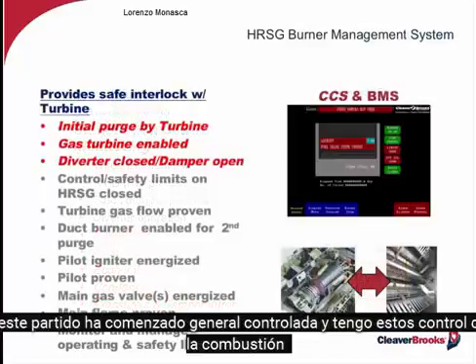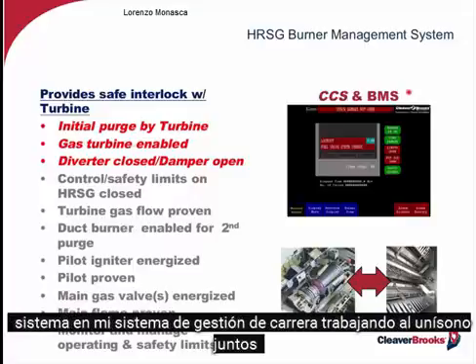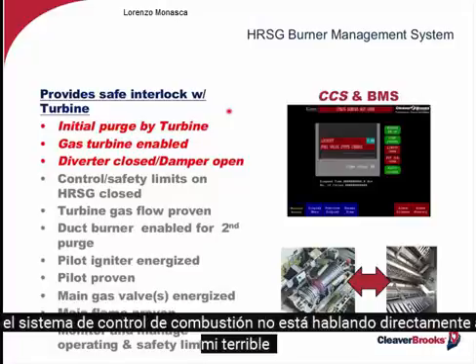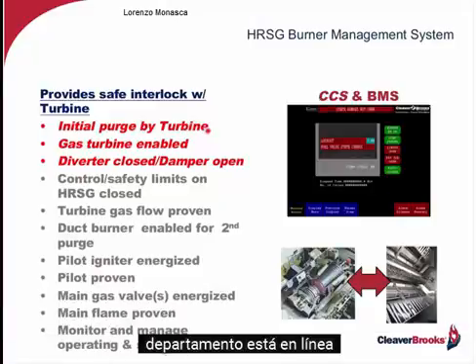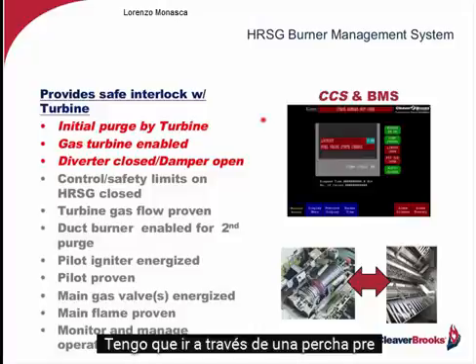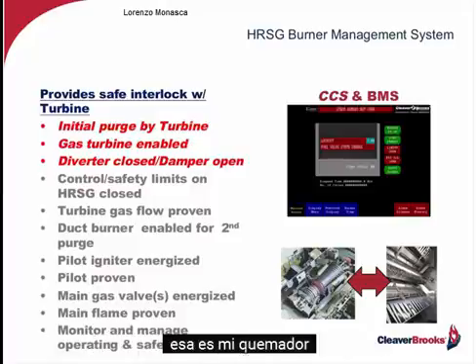As far as the overall control, I've got the combustion control system and my burner management system working in lockstep together. The combustion control system is now talking directly to my turbine. The turbine is online. I've got to go through a pre-purge. The combustion control system will monitor that. The gas turbine is then enabled. We fire off. That's my burner.